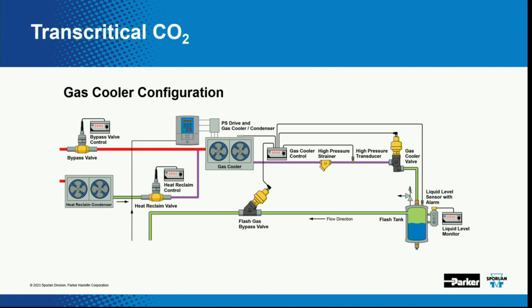That is being controlled by the gas cooler valve. So that gas cooler valve is controlling the pressure in that. And what's happening is there's a huge pressure drop going through that valve. So that's kind of like our expansion device. That's expanding into the flash tank, which is also called a vapor liquid separator. So from the flash tank, we take that liquid and we just feed that liquid to our cases, just like normal. Bada boom, bada bing.